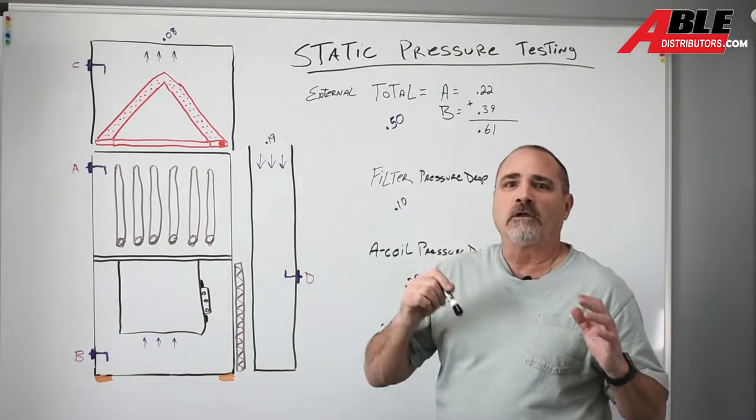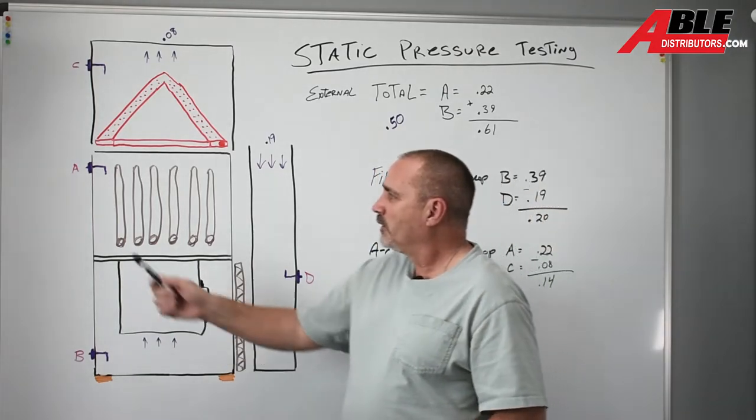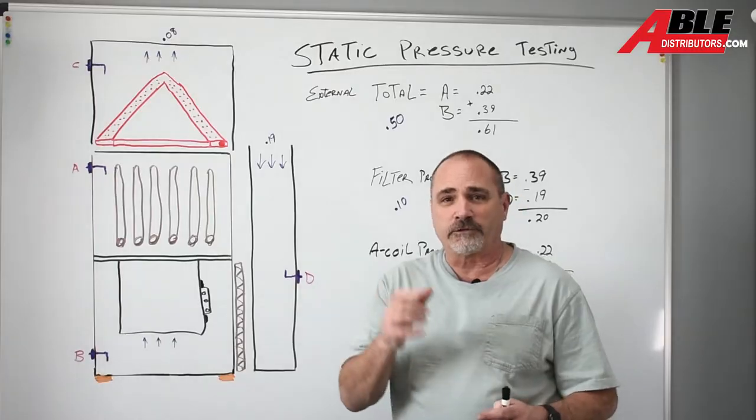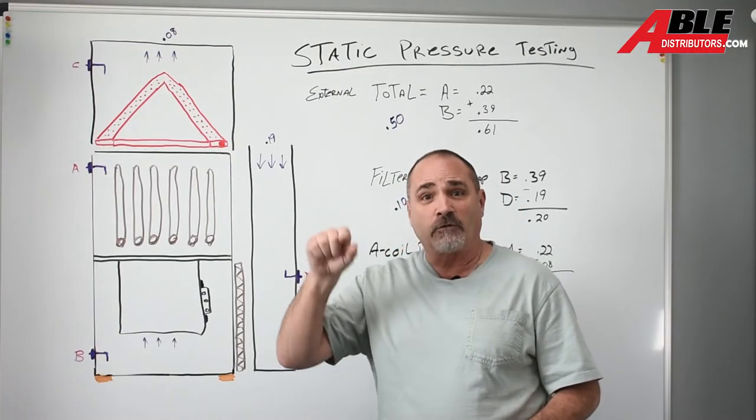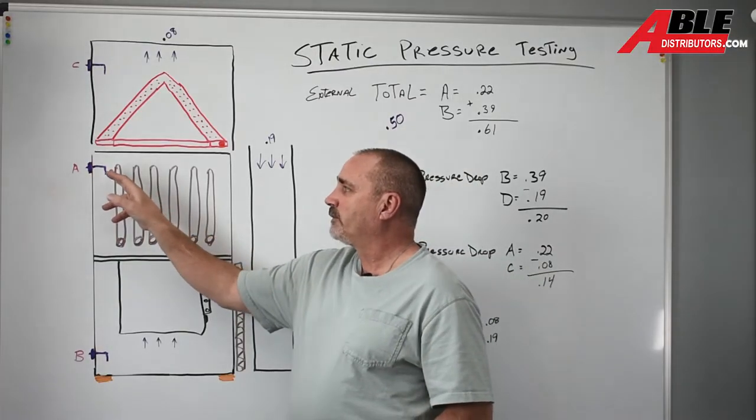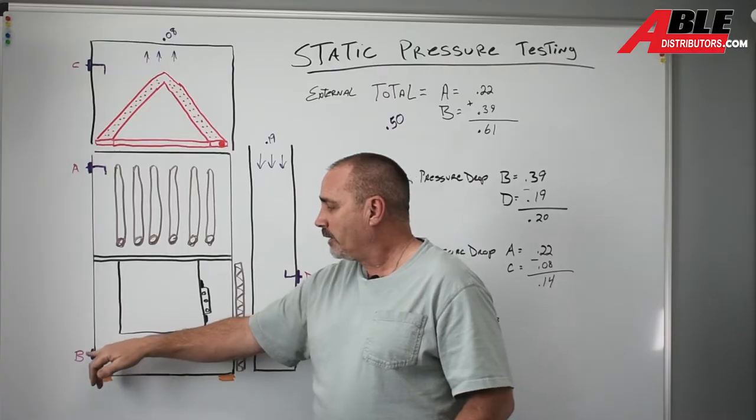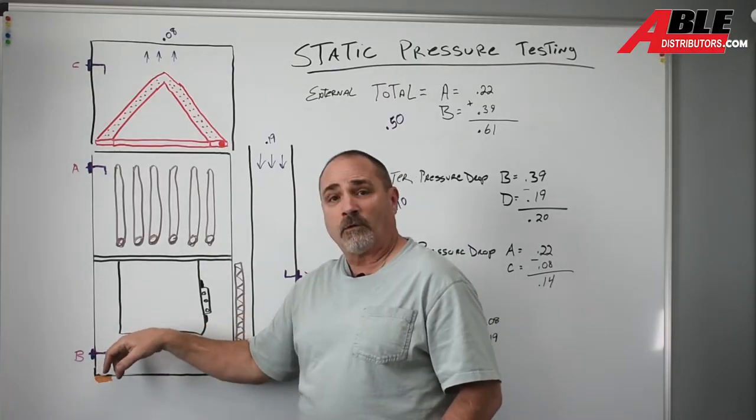To check total external static pressure you're going to drill a hole in the side of the furnace. Yes, it is a hole in the side of the furnace. I suggest a step bit so you don't go all the way through. A hole in the front top of the furnace in the side below the A-coil and then a hole in the side of the furnace in the blower compartment.